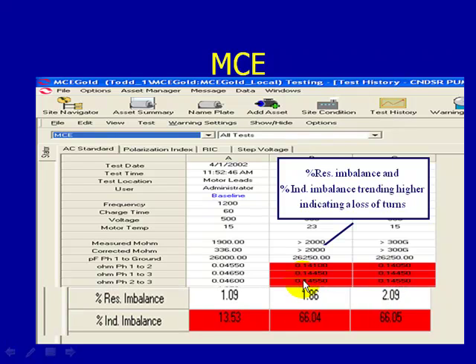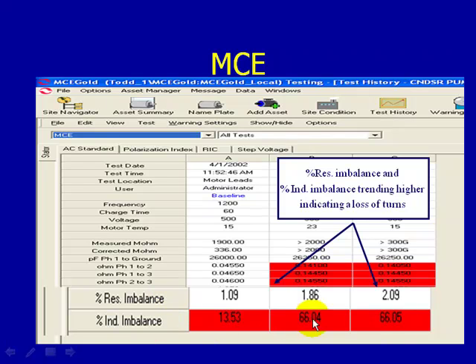How would we analyze a stator fault with our MCE technology? As we see here, we're looking at resistive imbalance and inductive imbalance. If we change resistance in one of the phases, that will create a resistive imbalance, potentially causing current imbalance and excess heat. For inductive imbalance, as we lose turns in one of the phases, that will change the inductance measurement — creating a higher inductive imbalance and causing this number to go into the red and increase as you lose turns.